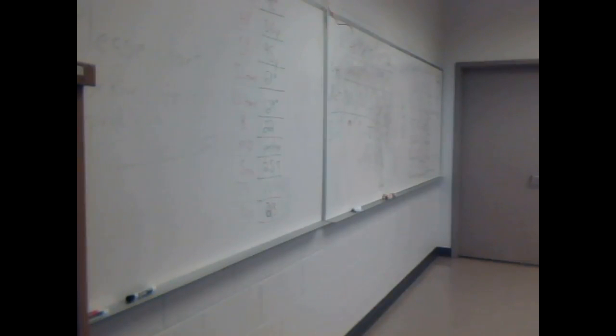Okay. So look where it says on the next right-hand comment. It says generally, high temperature applications, quote, air conditioners, operate with a 15 to 25 degree delta T through the coil. All right. Now I don't really agree with that. If you go to your Manual S put out by the ACCA, they'll tell you 14 to 21. But I got no problem using this. 15 to 25, is that what they're saying here?